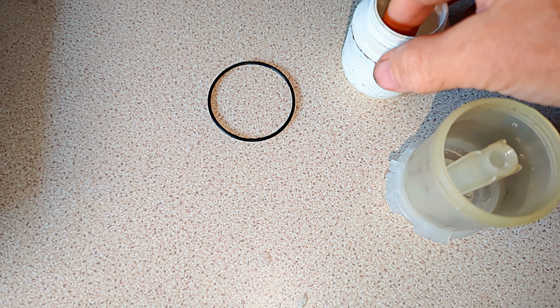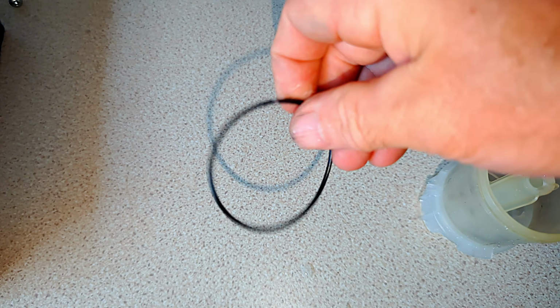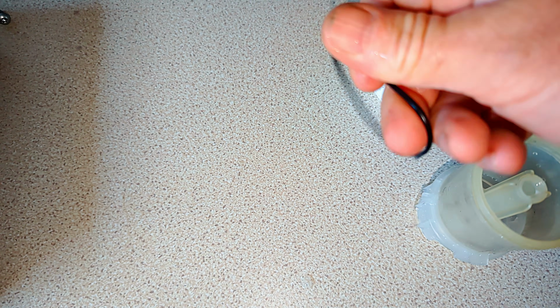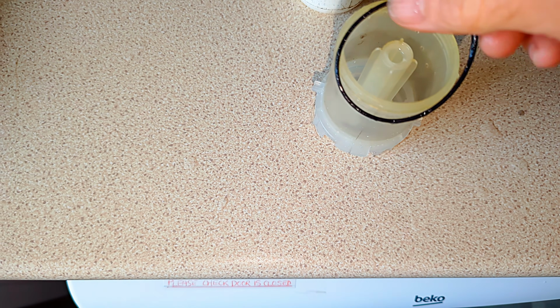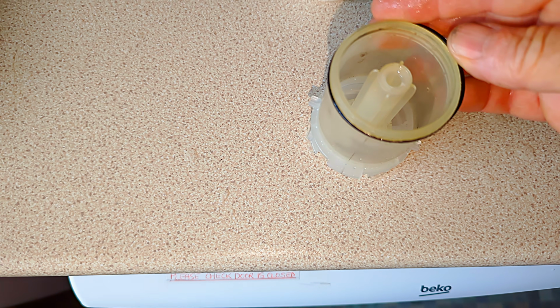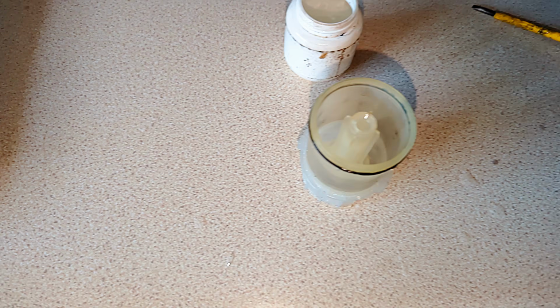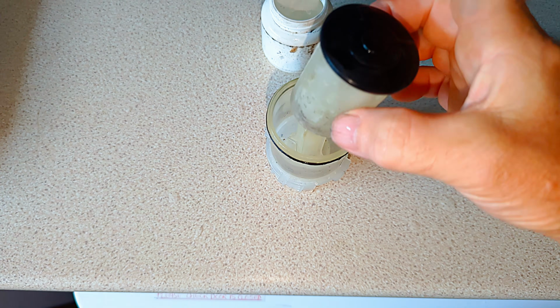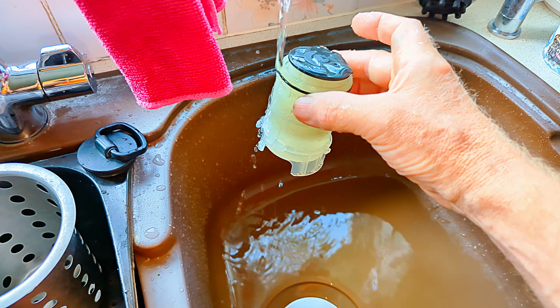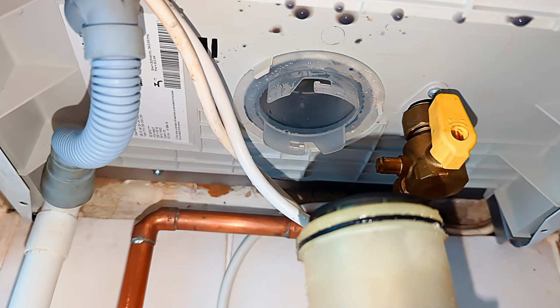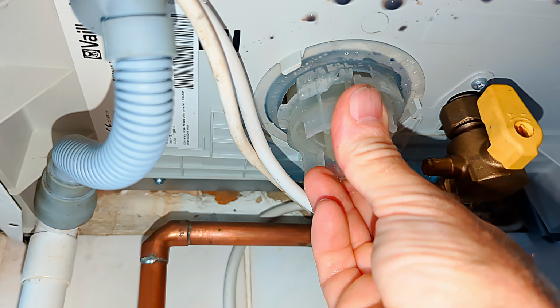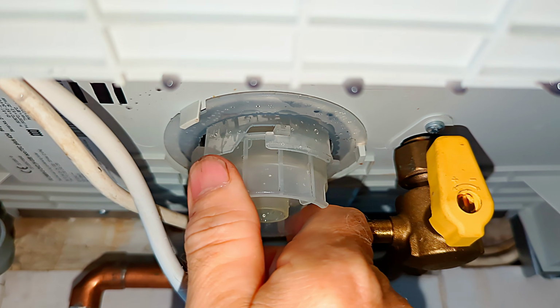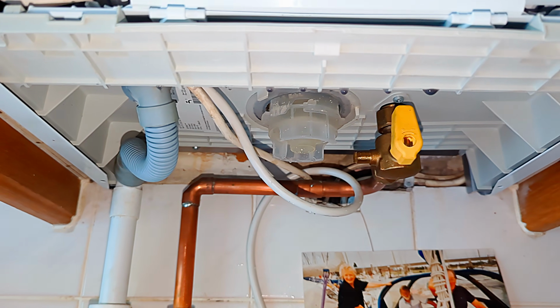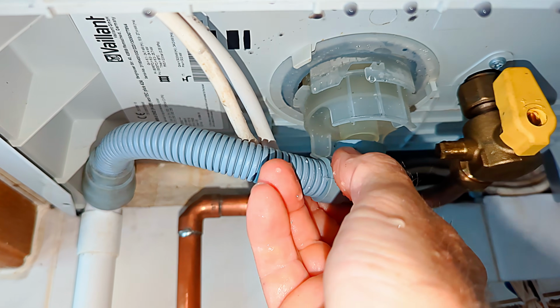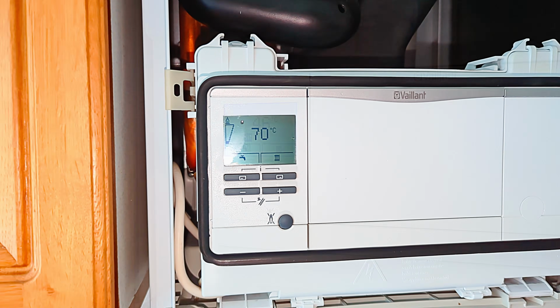I then like to take off the O-ring, give it a clean and then add a little bit of silicone grease to help it slip together, because like I said, this is a part of the boiler we need to maintain, so it wants to be able to come apart nice and easily. So take that off there, pop the float back in again, and then ideally add a little bit of water to the float like that. And then slide it into the outer part of the trap, put it into the bayonet connection, twist it around and pull it down slightly to lock it in position. And then finally, don't forget to reattach the rubber tube. There we go. That's the boiler all up and running again.